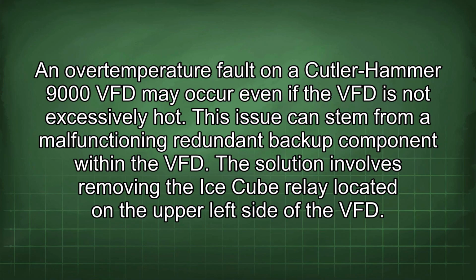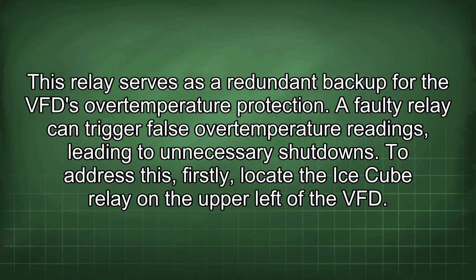An overtemperature fault on a Cutler-Hammer 9000 VFD may occur even if the VFD is not excessively hot. This issue can stem from a malfunctioning redundant backup component within the VFD. The solution involves removing the ice cube relay located on the upper left side of the VFD. This relay serves as a redundant backup for the VFD overtemperature protection. A faulty relay can trigger false overtemperature readings, leading to unnecessary shutdowns.